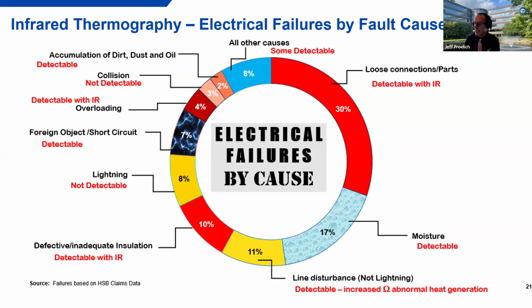Defective or inadequate insulation is another key cause. It's really derived from physical damage, abrasions or cuts in wires, aging, heat, moisture, rodents perhaps—something as simple as that—so keeping your panels in check, and possibly manufacturing defects. Signs or symptoms might be fraying, cracking, peeling, discoloration, exposed wires, and things of that nature.